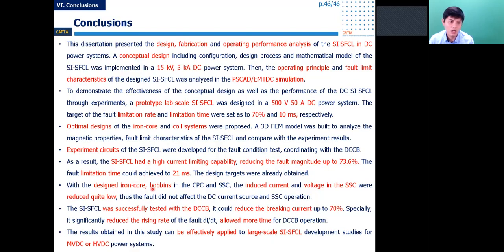With the design of iron core bobbins in the primary and secondary coil, the induced current and voltage in the secondary coil were reduced quite low. So the fault current did not affect the DC current source and secondary coil operation. The SI SFCL was successfully tested with the circuit breaker. It could reduce the breaking current by up to 70%, and especially it significantly reduced the rising rate of the fault current, di/dt, and allowed more time for the DC circuit breaker operation. The results obtained in this study can be effectively applied to large-scale SI SFCL development for the MVDC or HVDC power system.